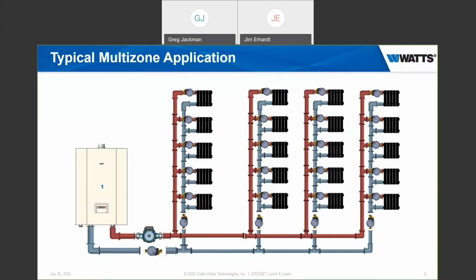But if we were to take a look at it, it's really the same situation that's happening with each vertical stack with the radiators. The vertical stack all the way on the right has the longest distance, the most piping. So it's going to have the greatest pressure drop. So if we don't balance not only radiator to radiator, but stack to stack, what'll end up happening is that stack all the way on the right, having the most amount of pipe and the greatest amount of pressure drop, is going to get starved for flow.